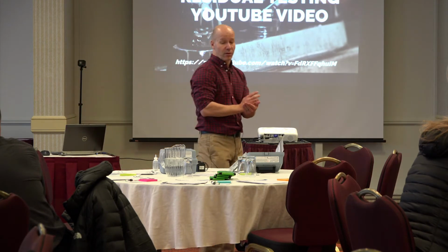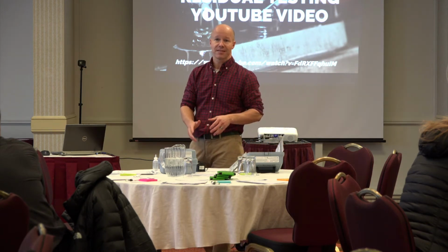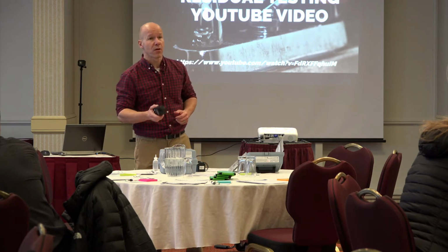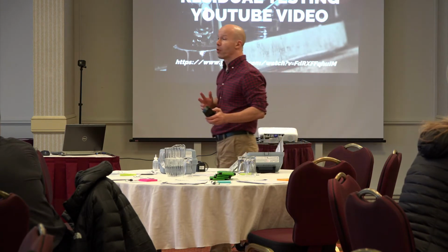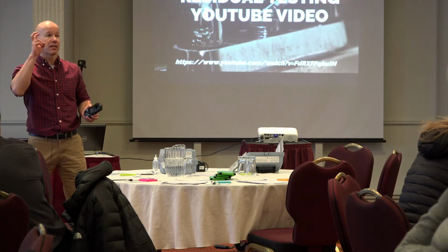So what is detectable? This is a field kit. You have to remember that this is a field kit. This is not an amperometric titration that's done in a lab. So for safety's sake, what we're communicating to operators is we would like to see it between 0.05 and 0.10 milligrams per liter for safety's sake to say it's detectable, right?